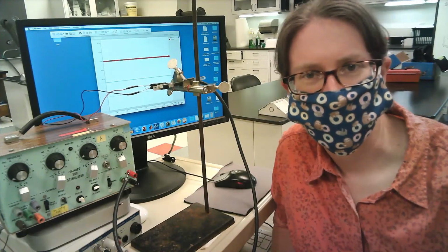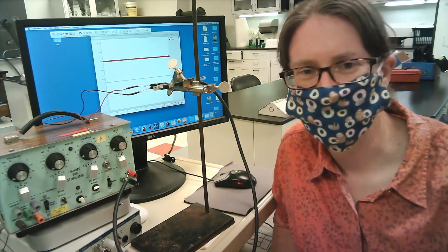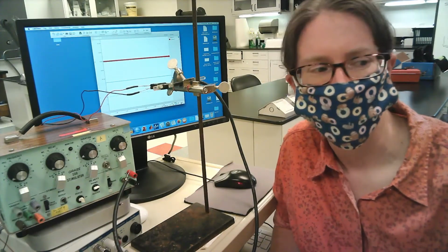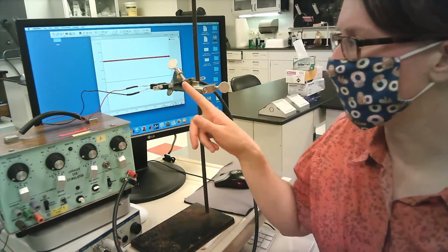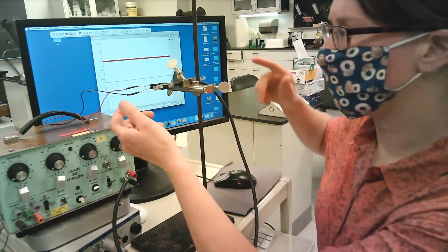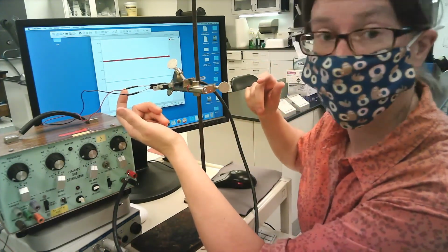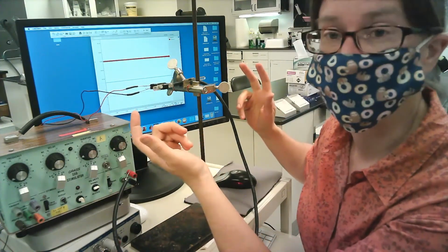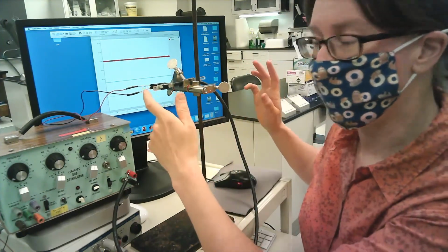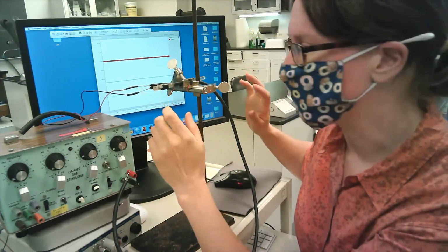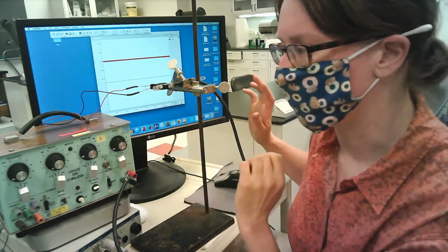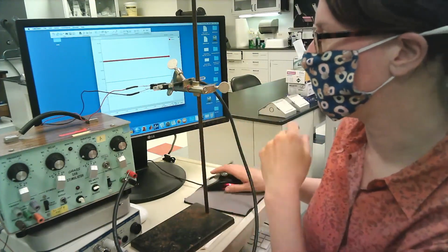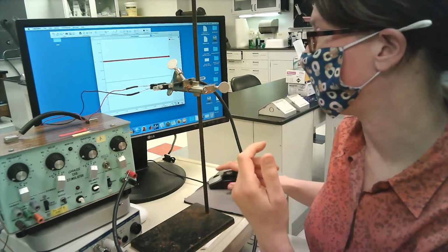Once you've got everything hooked up, you're now going to want to test everything and just make sure that your stimulator works, that your recording electrodes will record. So what I've done here is I've taken this stimulator and then I've taken my 2 needle electrodes here, those are my recording electrodes, and I've just connected them with each other for testing purposes. And you may wind up having to fiddle around a little bit with this configuration to get everything in contact with each other. But then I'm ready to start doing some testing. So I've loaded up LabChart, and I'm just going to start running that in the background here.